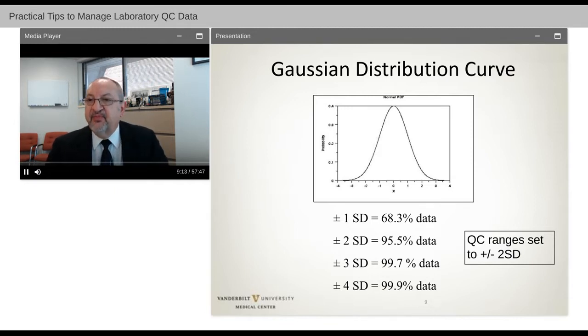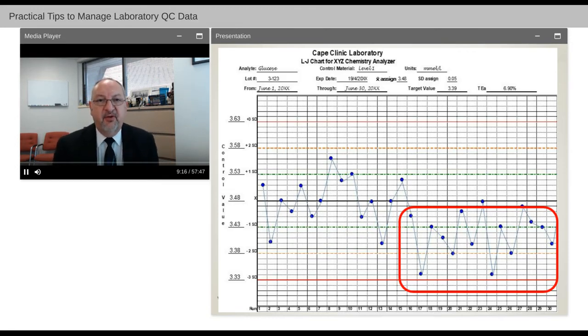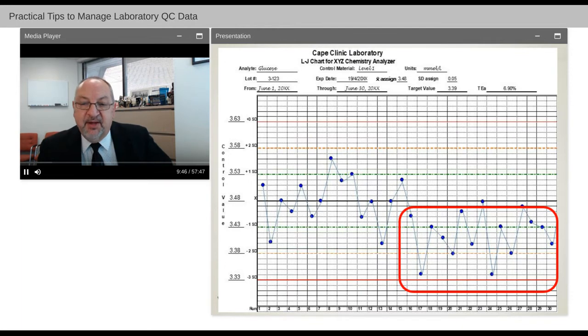In other words, we can measure over a period of several days a particular quality control sample, achieve a mean and a range of data around that mean, and within two SDs, we can predict future performance if we continue to analyze that sample or samples from that same quality control lot. So if we plot these, we can see most of the samples on this plot here fall within the mean, which is the big black bar in the middle, 3.48 for this glucose. And most of the plots within the first half of this graph fall within plus or minus two standard deviations, the orange dashed bars.